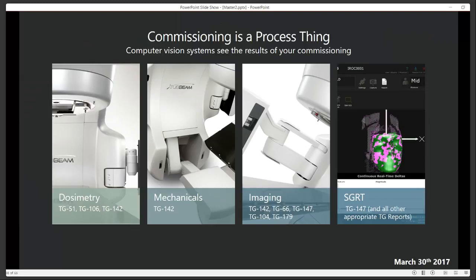And so a lot of times I'll get somebody that says, I have this SGRT system. When I kick the couch to 45 degrees, the system says that the phantom moved, and I know the phantom didn't move because the phantom doesn't move. And I'll ask them, well, when's the last time you did a Winston Lutz or checked your couch walkout? And a lot of times it's, well, when I did my commissioning, or maybe last time I did my annual.